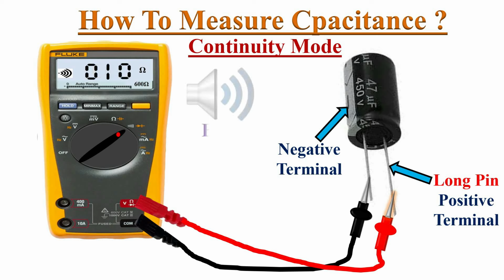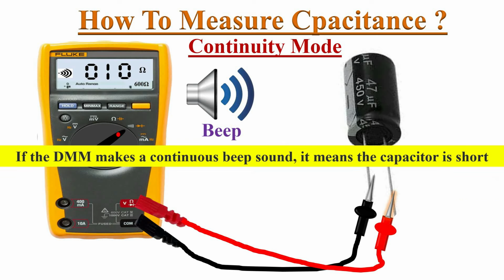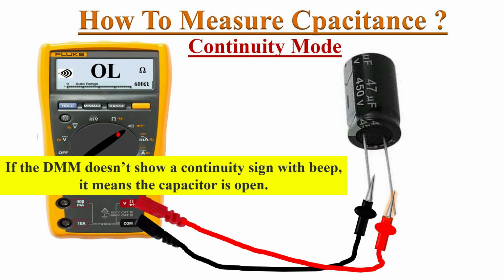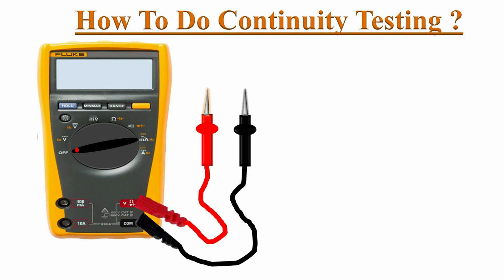If the meter shows proper continuity with a beep sound and gradually increases and shows an OL reading, it means the capacitor is in good condition. If the multimeter shows continuity with a beep sound continuously, without any increase, it means the capacitor is shorted. It's faulty. If the multimeter doesn't show continuity with a beep sound and shows OL reading, it means the capacitor is open. It's faulty. Now let's discuss how to check continuity with a multimeter.